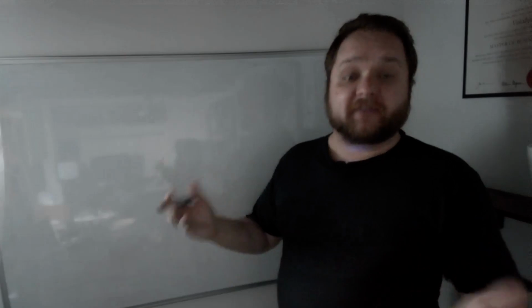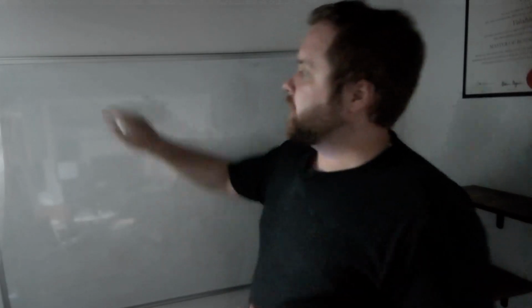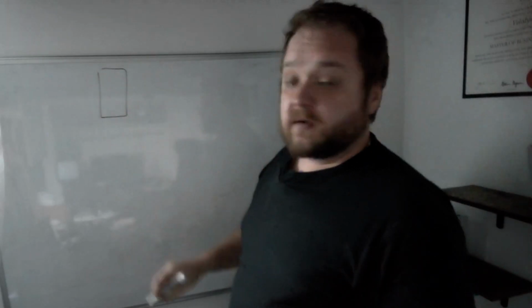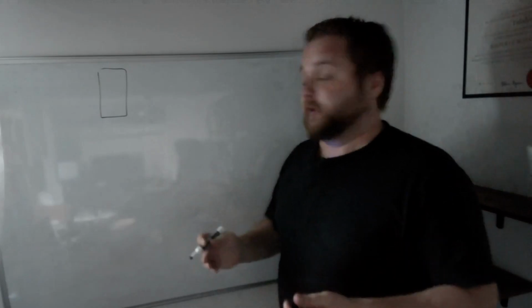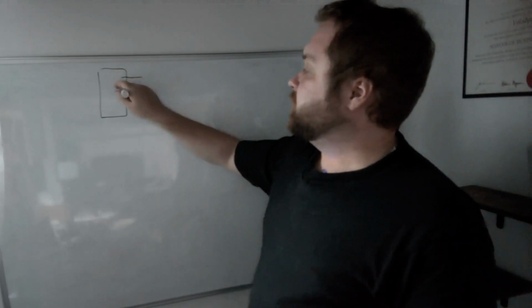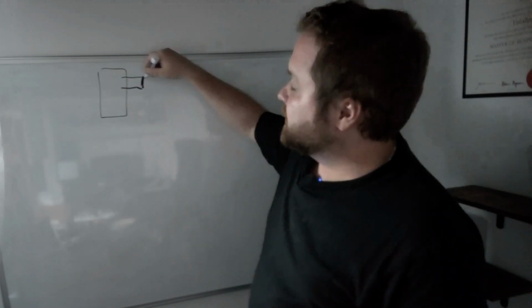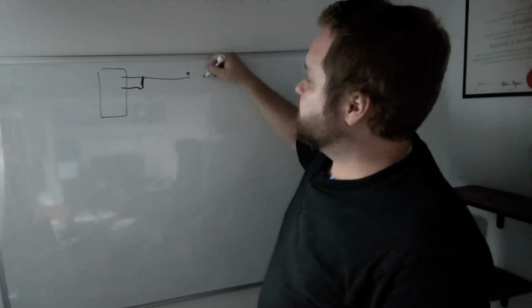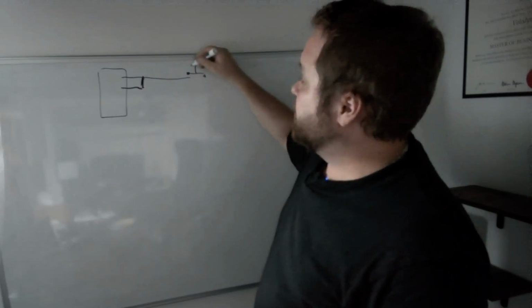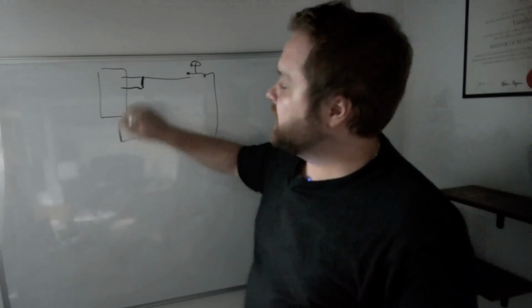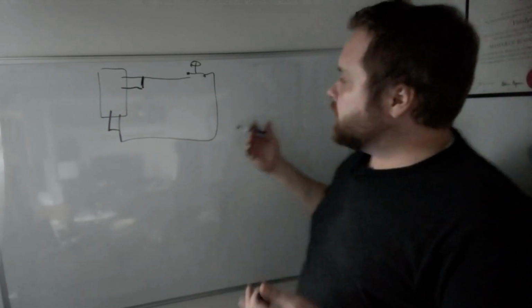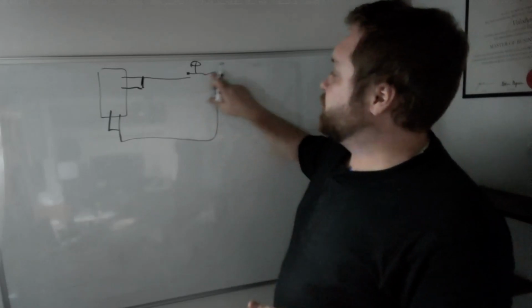So this is the part where we get to some FAQs, right? If you have a dual channel safety relay, these are some of the things you should not be doing, right? So if you have two channels that need to be 24 volts confirmed, and then sending a single wire down a series of push buttons that are not dual channel rated, and so here at the end, you're again splitting off that signal. You should obviously not be doing weird things with your push buttons, right?